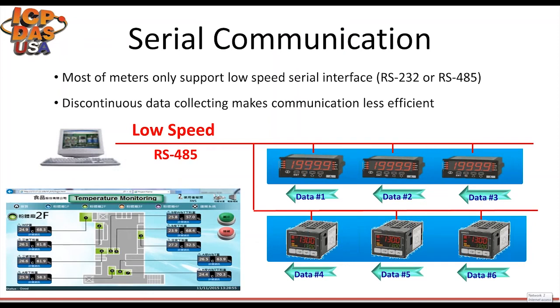For serial communication, the conventional approach to read back Modbus data is reading from the meters or other Modbus devices one by one via RS-485, as shown in the picture. However, the speed will be very slow. Data transmission will become a bottleneck. Data collecting will be discontinuous, no matter how fast the performance of the PC is. The speed of RS-485 itself is not fast enough, and the speed problem still cannot be solved.